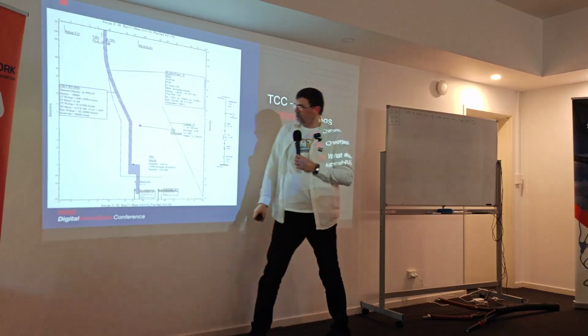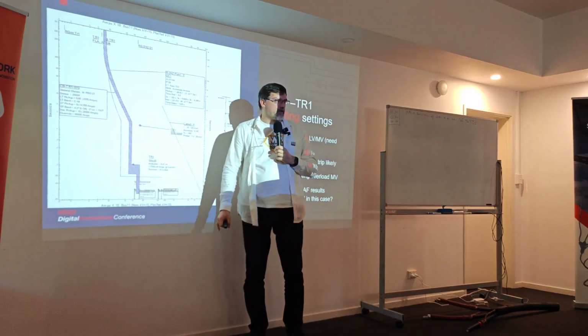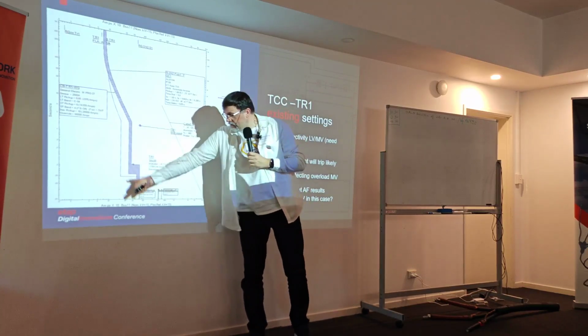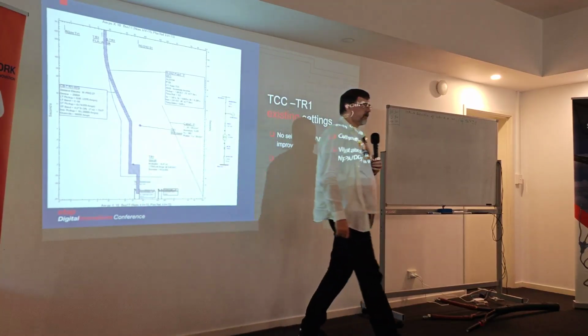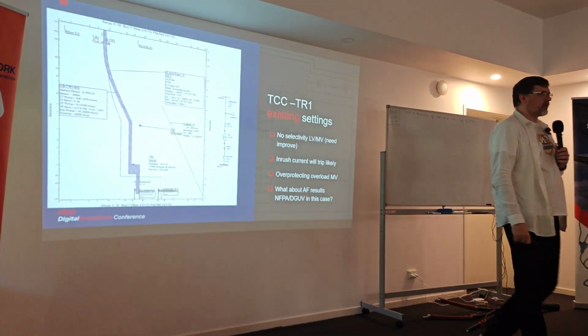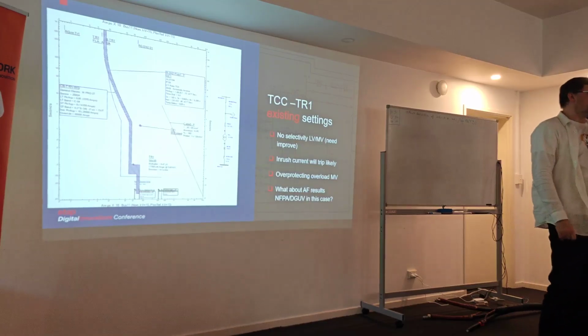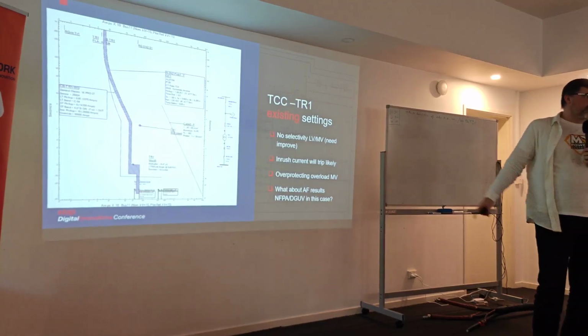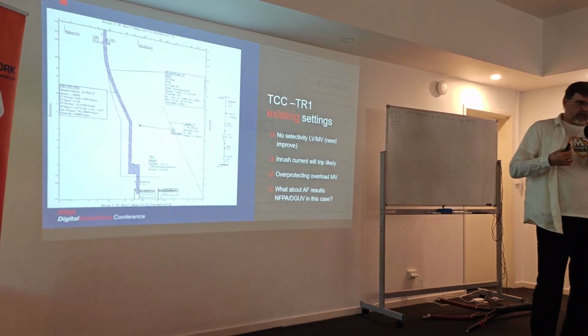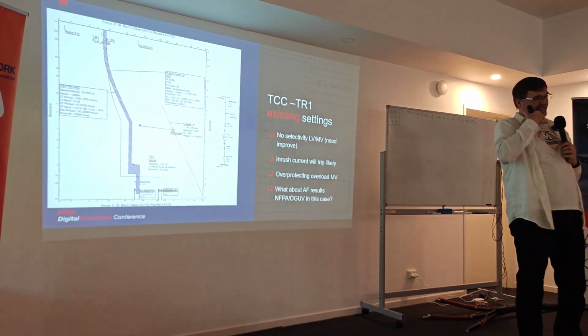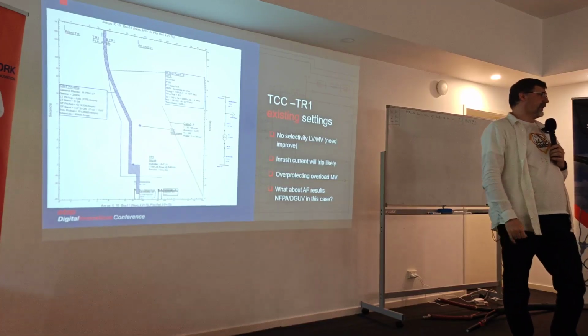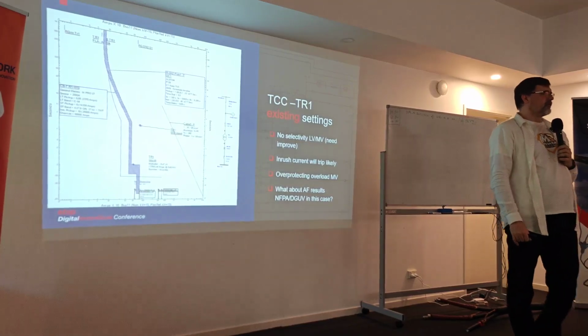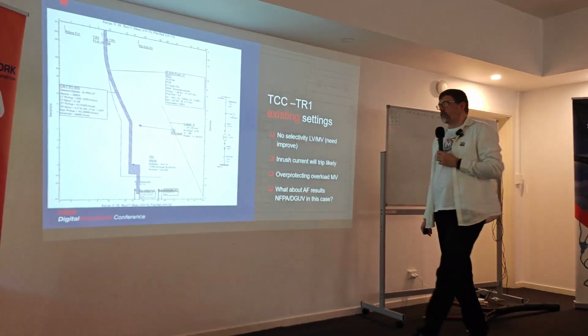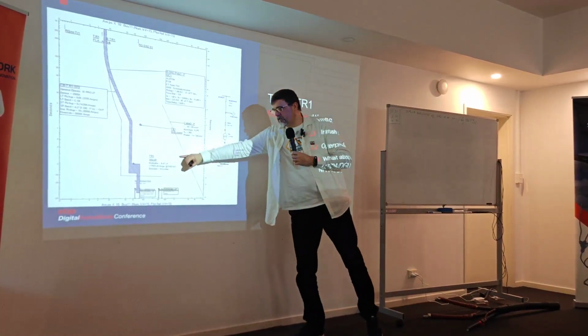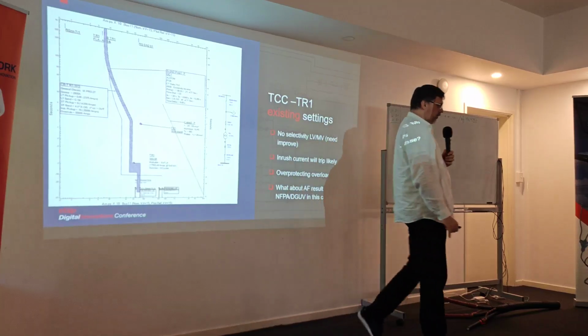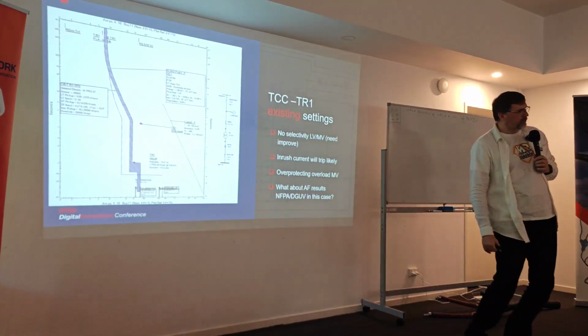My main problem on the project is not really arc flash all the time. It's protection. Generally that's the existing case, and this is bad. You keep tripping medium voltage, so it's barely possible to even energize the transformer. No one wants it, because in most industrial cases you have to call a different guy. And if you have to call at 2 a.m., like, okay, who will come? And the whole production is stopped. So protection is one of the things that is constantly there, so you want to be well protected.